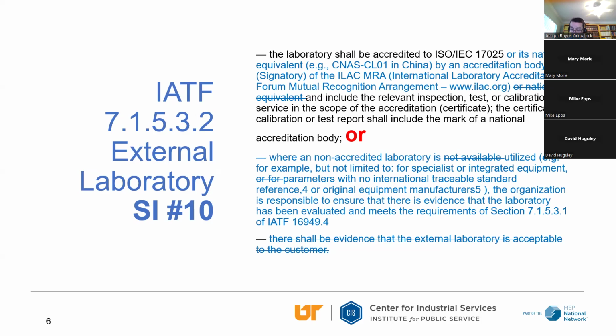When you use a non-accredited lab, meaning they're not A2LA, they're not 17025, that's okay. But your organization needs to document and show evidence that you're okay with them and that they meet the requirements of IATF clause 7.1.5.3.1, which is you've got to have an internal lab scope. So you've got to have a copy of their lab scope, and that lab scope needs to include what testing or calibration service they're providing. Where companies will get in trouble is if they're using a calibration company to calibrate a weight scale or balance. It's okay to use a non-accredited lab or service, but you need to have their lab scope. And if their lab scope doesn't include calibration of balances or scales, then you're in violation of this requirement of the standard.